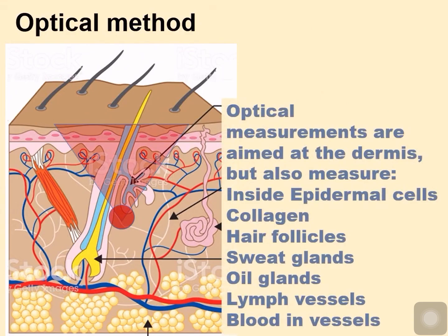And then optically, if you want to measure it optically, which is ideal because it's totally non-invasive, you would focus the light into the dermis. You have to decide how deep into the dermis to go, how big the spot size is, and how vertically selective you'll be with your optical system to try to optimize your signal, because you're going to measure everything in there. You're going to see hair follicles and the vessels and glands. So it all gets collected, and you try to optimize your optics to get as much interstitial fluid and plasma as possible.